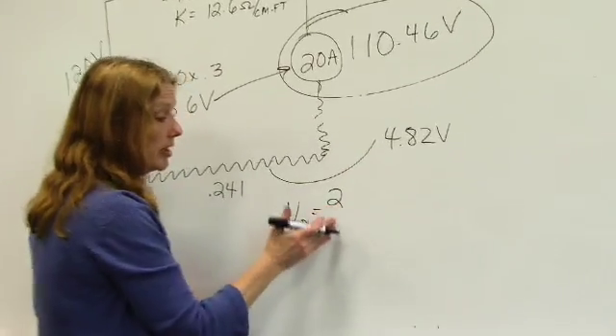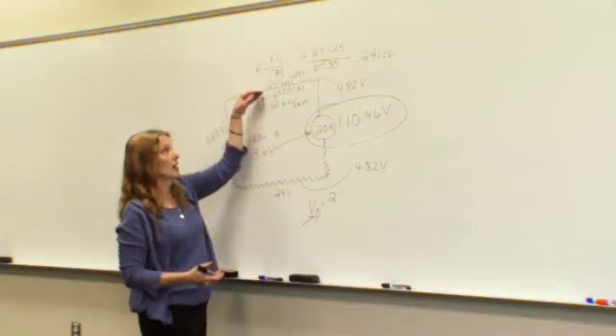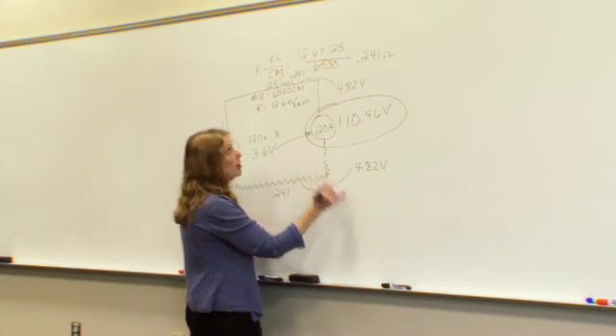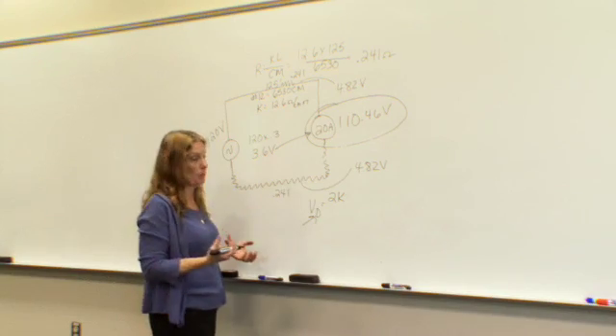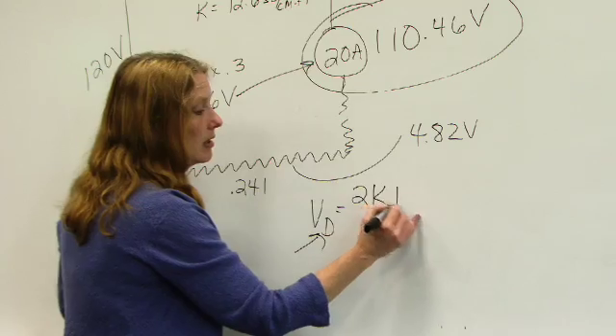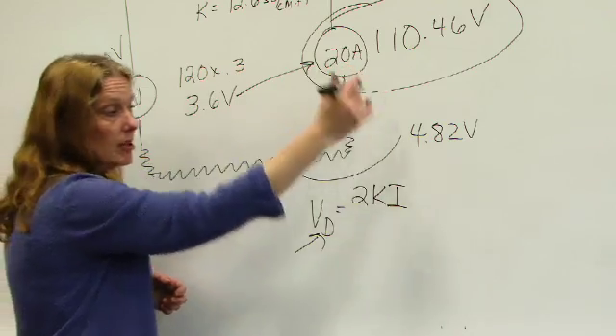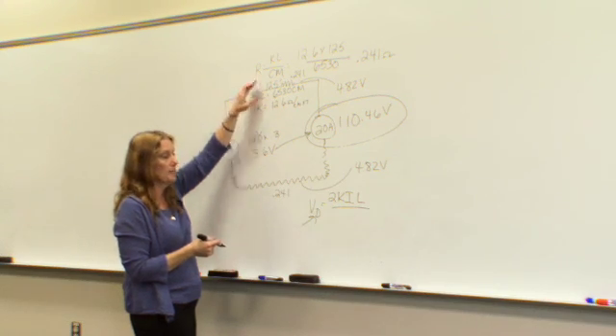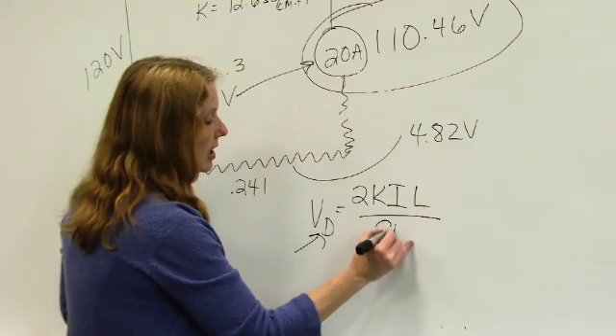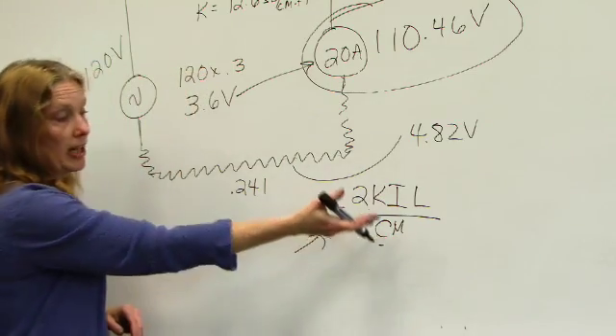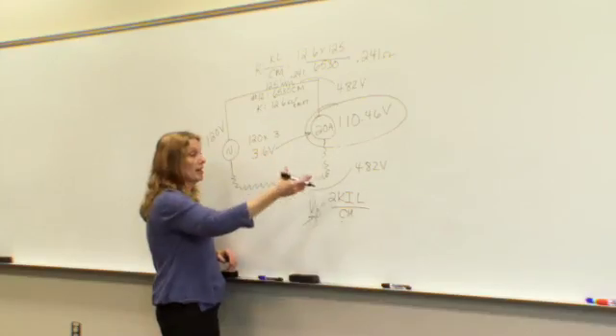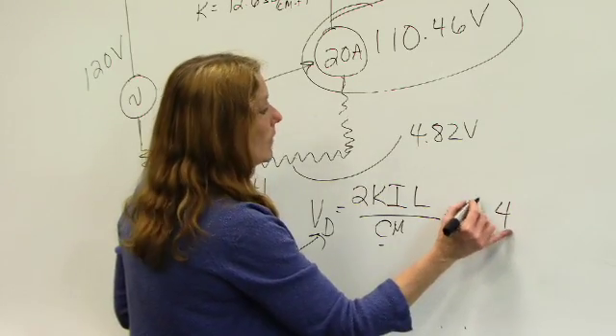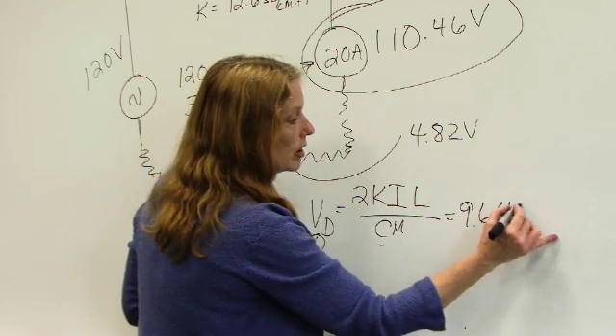I have a number 2, and that 2 signifies going to my load and coming back from my load. K, which we already know about, that's that constant 12.6 in this case that we use the code book for. I, which is my current, 20 amps. L, which is that length, a little bit too long for this circuit at 125 feet. And circular mil area, once again we have that circular mil area. Plugging all those numbers in, just like we had, we end up coming up with our 9.64 volts.